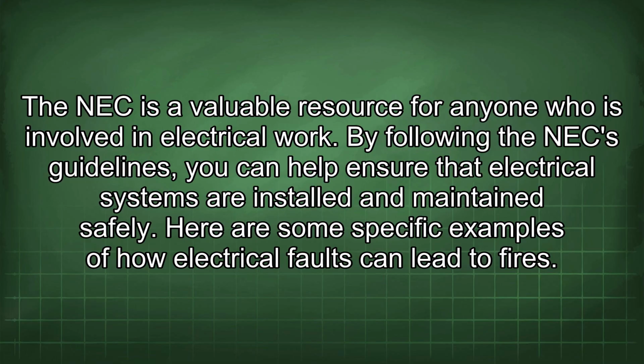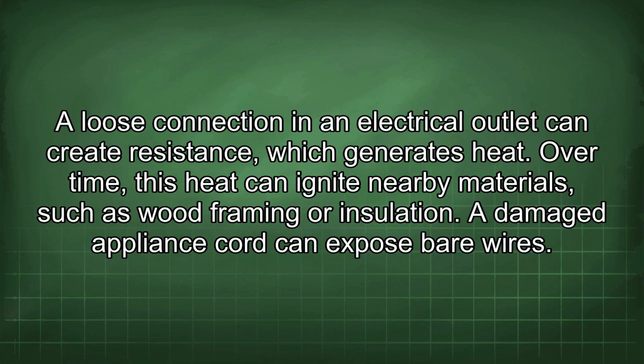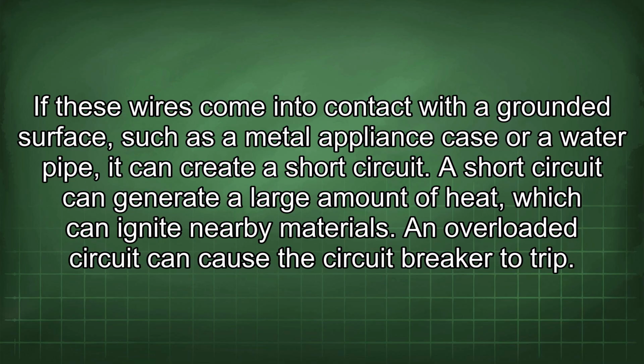Here are some specific examples of how electrical faults can lead to fires. A loose connection in an electrical outlet can create resistance, which generates heat. Over time, this heat can ignite nearby materials such as wood framing or insulation. A damaged appliance cord can expose bare wires. If these wires come into contact with a grounded surface, such as a metal appliance case or a water pipe, it can create a short circuit. A short circuit can generate a large amount of heat, which can ignite nearby materials.